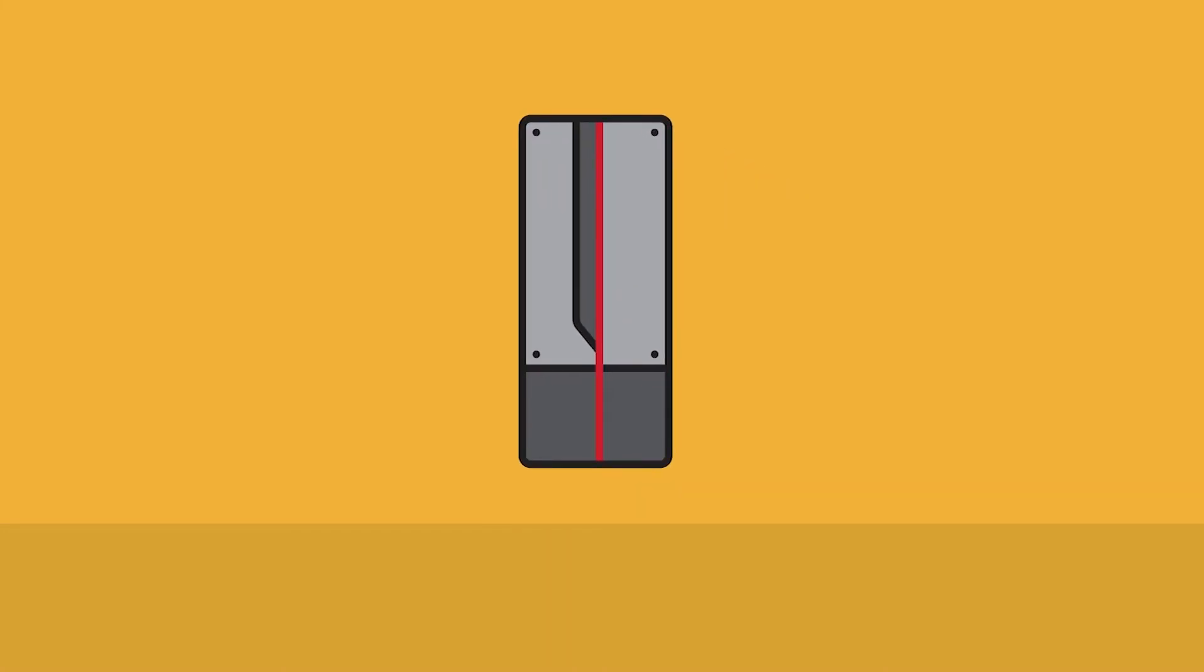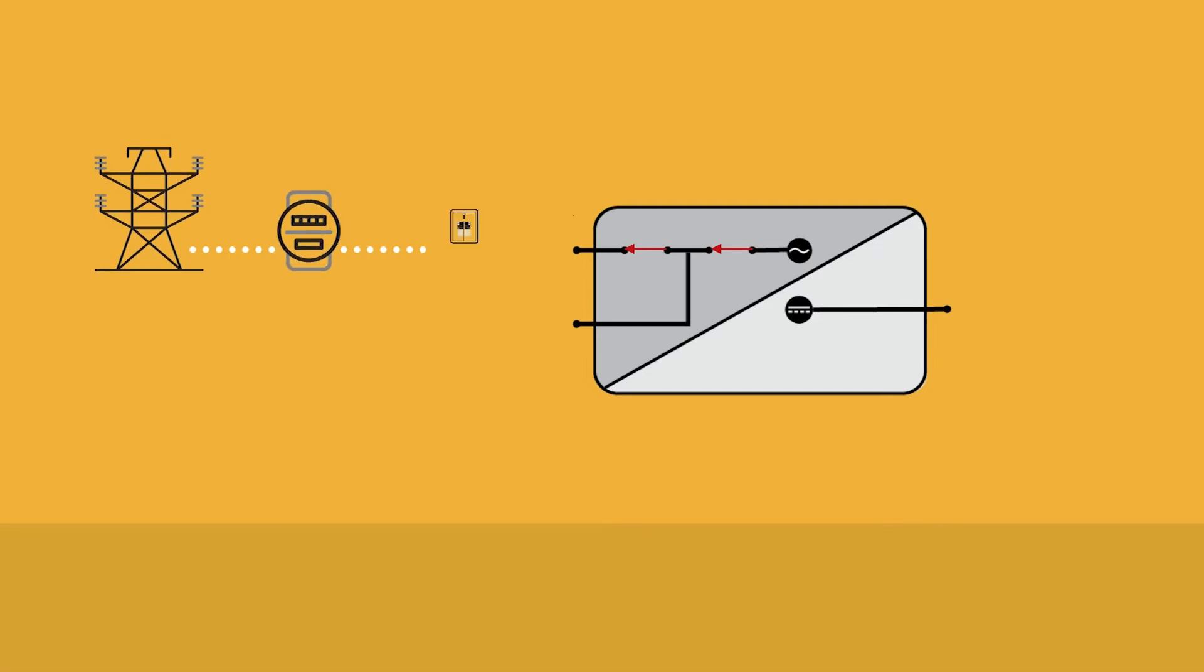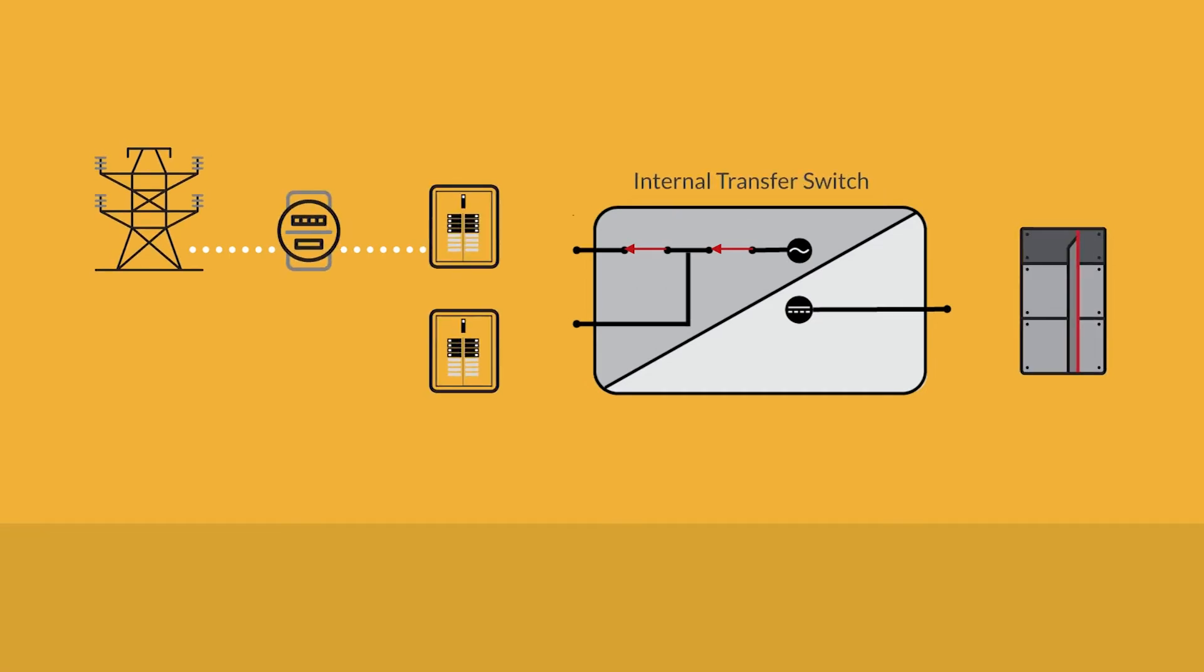However, the hybrid battery-based inverter offers additional built-in features that allow battery backup. This is possible due to its internal transfer switch. A hybrid battery-based inverter such as a Radian or Mojave have built-in transfer relays to alternate between states of inverting and accepting an AC source. From the input of the inverter, a source wire is fed from the house main panel to the AC input of the inverter, versus the AC output of the inverter is connected to a protected loads panel.